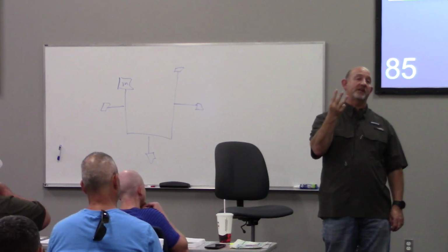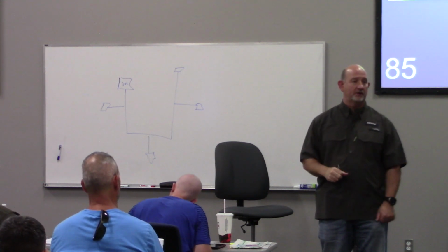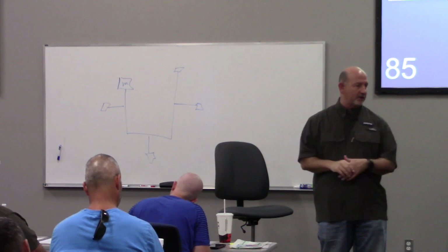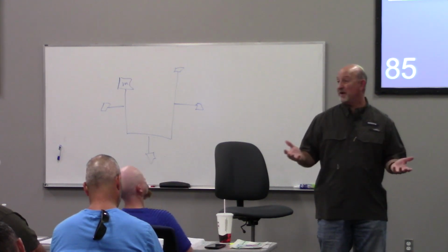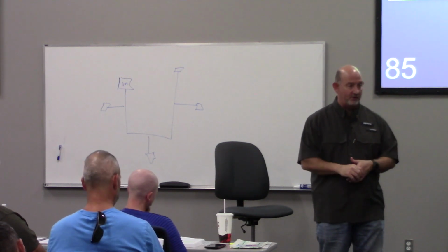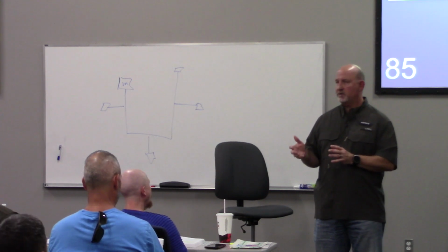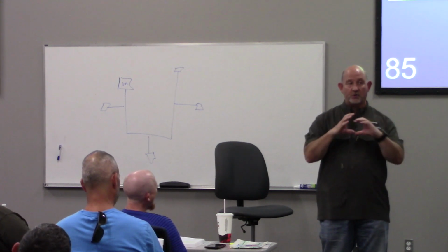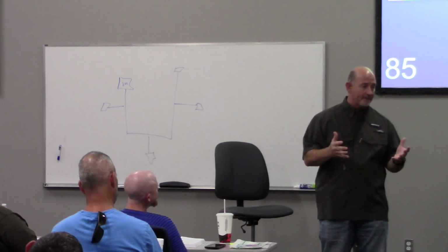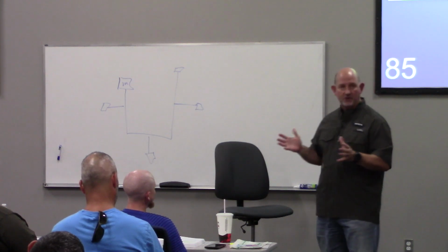How about a 3 by 33 and a half? That's 100 square inches. Do you agree that's okay? Because the minimum dimension was at least 3, and you gave me at least my 100 square inches. Make sense? A 4 by 25, a 10 by 10, right? A 12-inch round, whatever, right? So now why did I say a 12-inch round? Because if I still need that 100 square inches, do you agree a 3-inch round will meet my minimum 3 inches in dimension, but it's not going to give me my 100 square inches of area. Make sense? You guys okay with that?